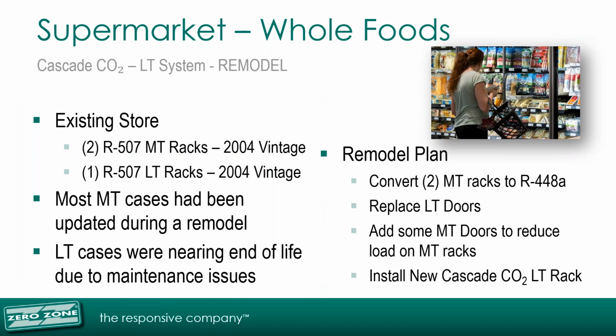During the NASRC event in January 2020, Mike Gallinger from Whole Foods, Brad Pearson and Russ Deal from SEER2, and Mike Hoffman from ZeroZone presented on a recent remodel. The existing store had 3 rack systems with R507. The low temp rack and cases needed to be upgraded as they were near end of life. This provided an opportunity to reduce the store's weighted average GWP.